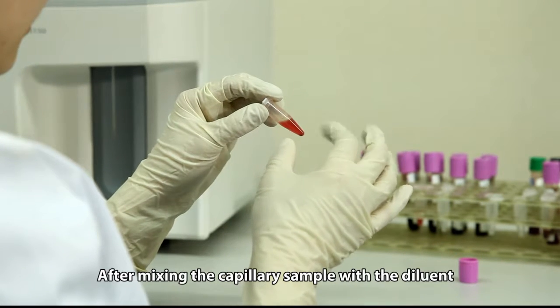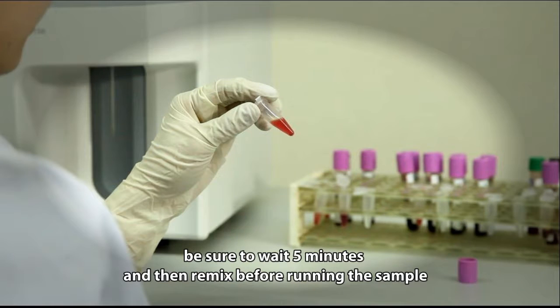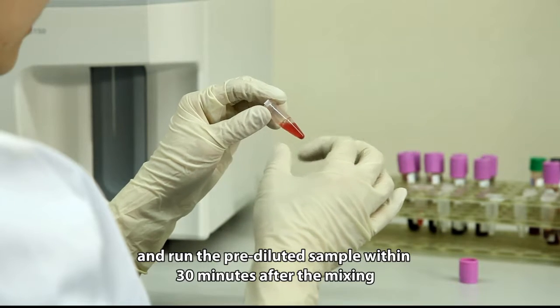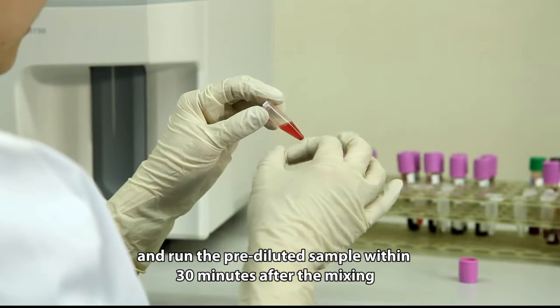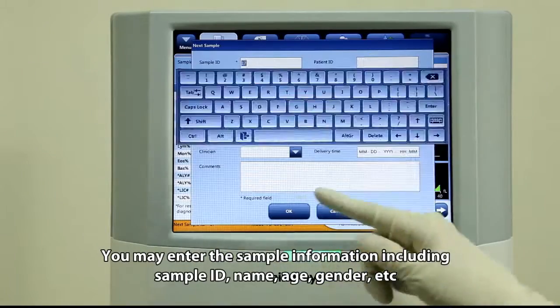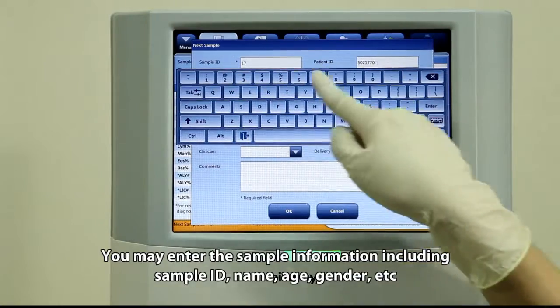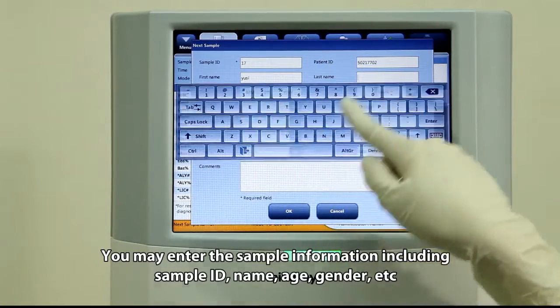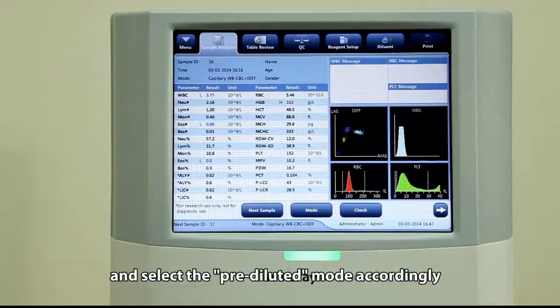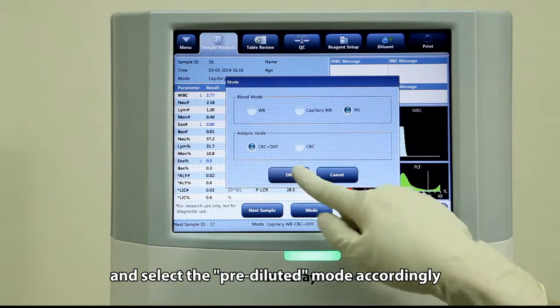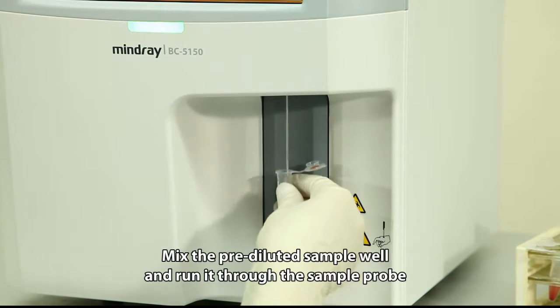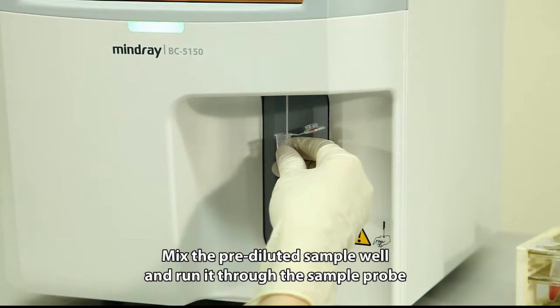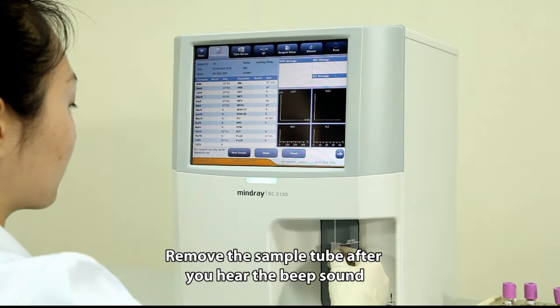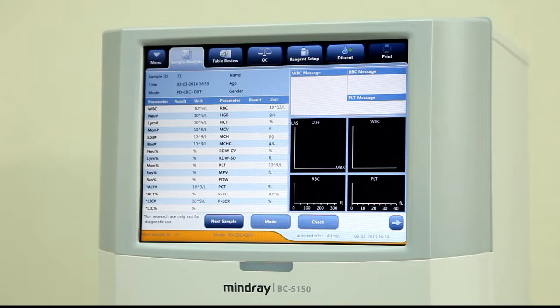After mixing the capillary sample with the diluent, be sure to wait 5 minutes and then remix before running the sample, and run the pre-diluted sample within 30 minutes after the mixing. You may enter the sample information including sample ID, name, age, gender, etc. and select the pre-dilute mode accordingly. Mix the pre-diluted sample well and run it through the sample probe. Remove the sample tube after you hear the beep sound.